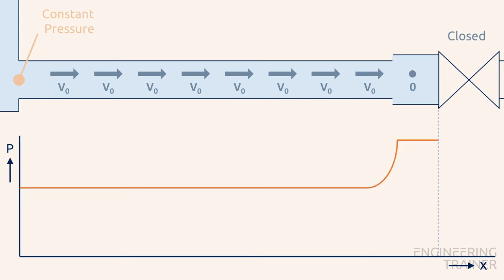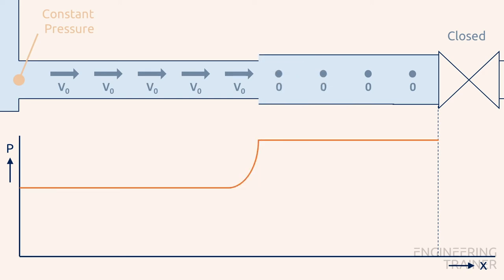Depending on the details of your system this pressure increase can be significant. The velocity of the water just upstream is now also brought to a halt. This is actually the result of the pressure gradient in the line. This pressure step yields a net force to the left which is the force that stops the neighboring water. This effect continues all the way through the pipe which is called a pressure wave.